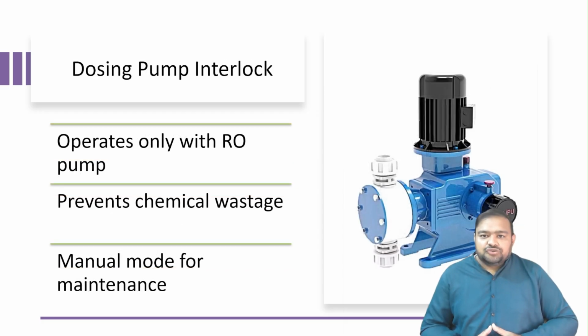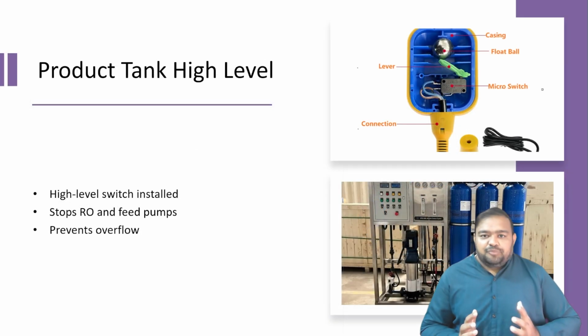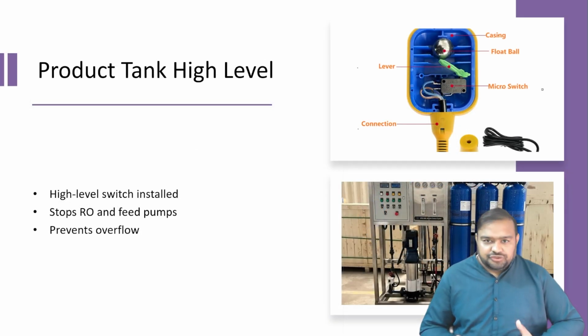The dosing pump operates only when the RO pump is running. In auto mode, when the RO pump is on, the dosing pump will be allowed, and when the RO pump is off, the dosing pump will be stopped. In manual mode, dosing pumps can be operated independently, but electrical protections remain active. The product water tank includes a high-level float switch. If the product tank reaches high level, the RO pump must stop, the feed pumps must stop, and the system must remain in standby. This prevents overfilling and water wastage.